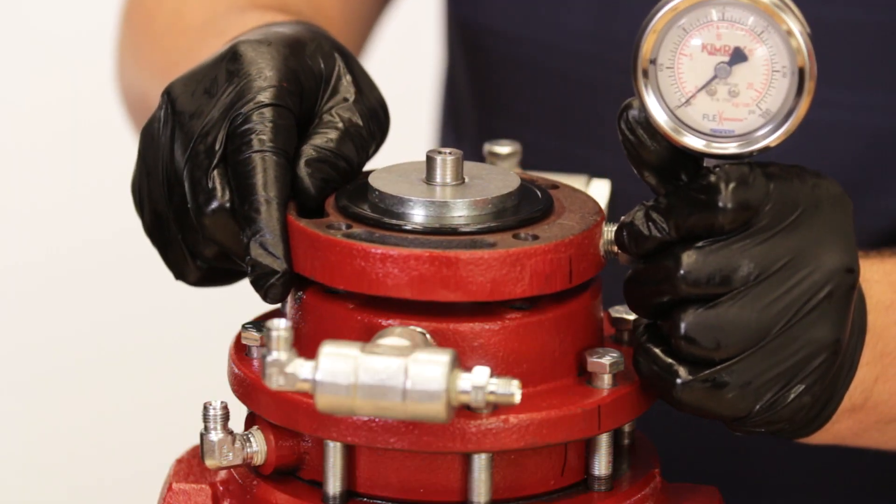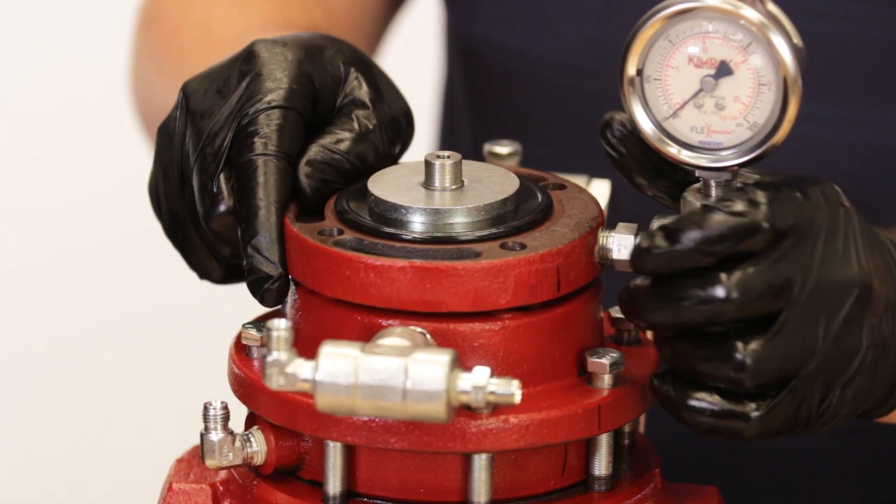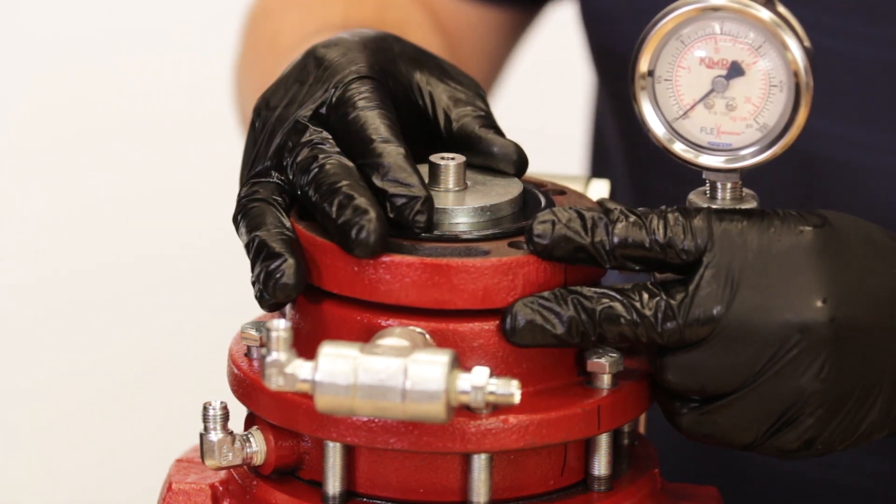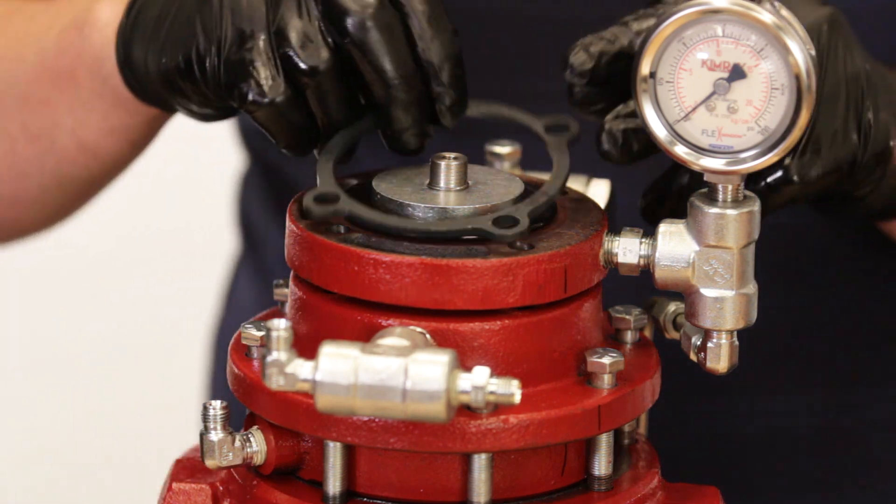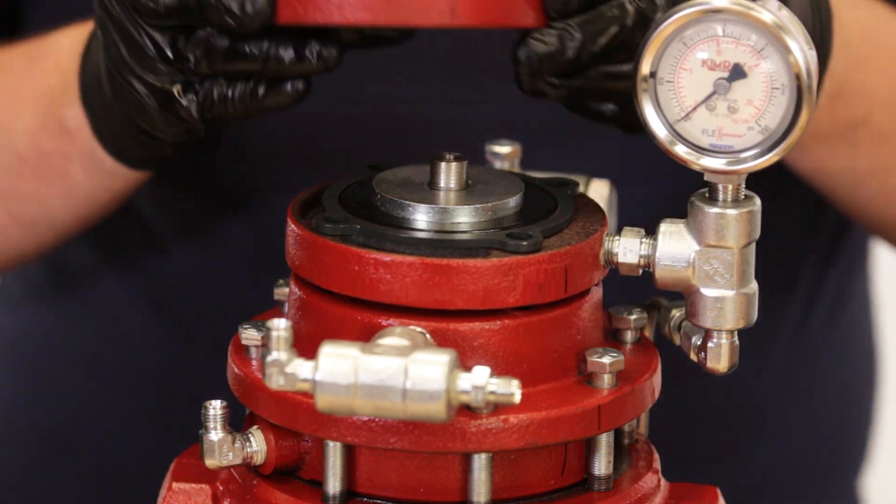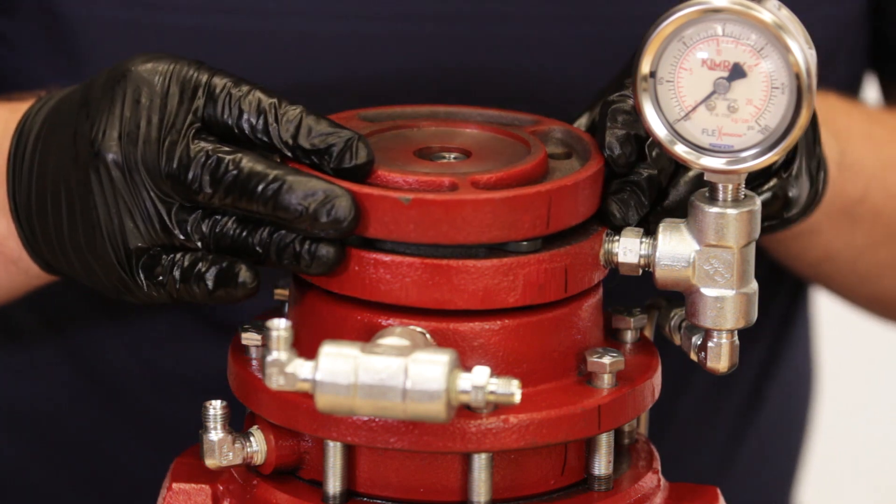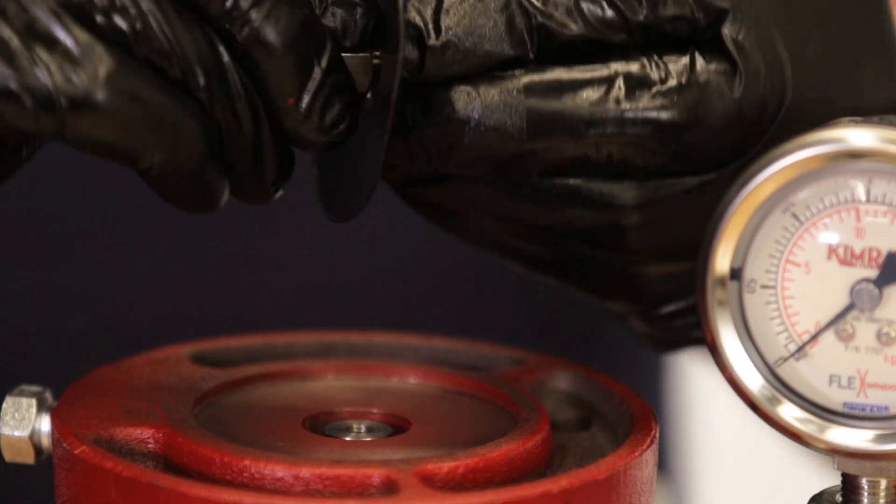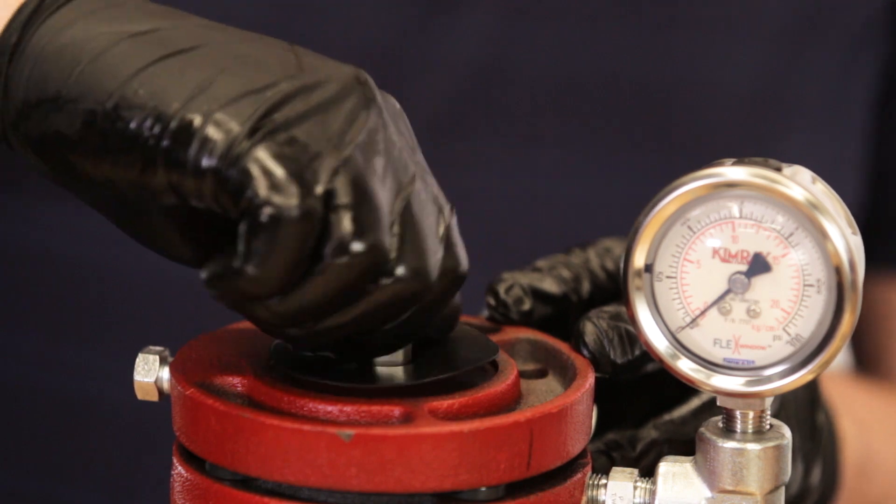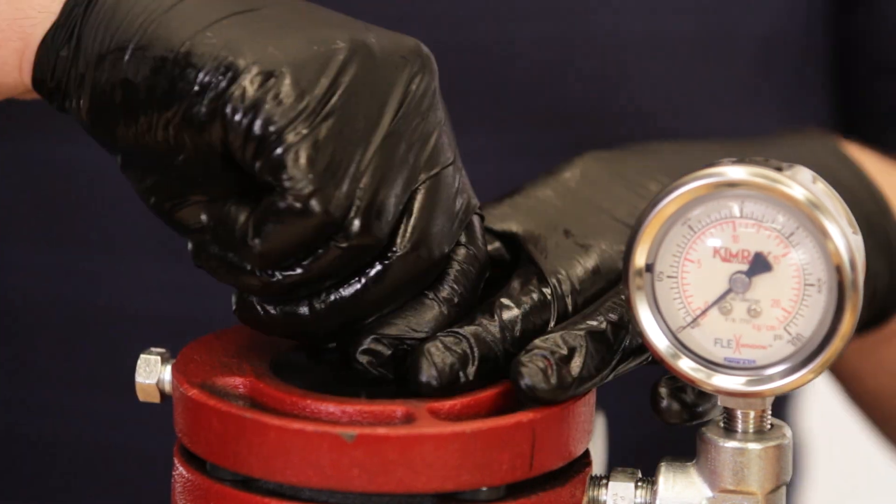Install the lower pilot housing assembly back onto the upper housing, making sure that the diaphragm isn't pinched or off center. Place the spacer ring around the diaphragm, being sure to align the bolt holes with the upper housing. Place the upper pilot housing, using your marks to keep it aligned. Thread the pivot screw through the diaphragm, keeping the convoluted side down. Carefully hand start the pivot screw to ensure it is not cross-threaded, then tighten it until snug.